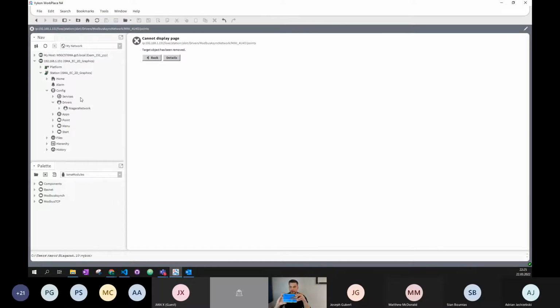So if we have a Mac36, this introduction will be more about BACnet, but then you will get the reference, because in BACnet, the Mac36 has routing enabled. So if you have devices connected to the RS485 bus over BACnet MSTP, and you discover the IP device, you discover the Mac, you also have access to all the modules which are connected to the RS485.